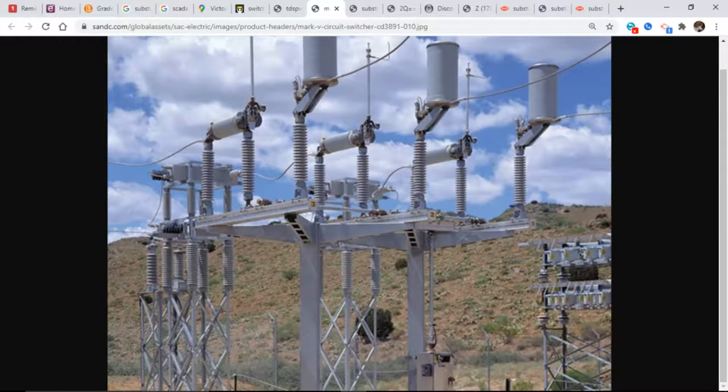Batteries. Hey, you bring up the question, and it was supposed to come up a little bit later once we got through this. We'll go ahead and go through it now. All of your substation automated equipment, including the communications and SCADA, does not run off of 120, 240. A 120, 240 transformer is installed in a substation to charge a battery bank, and that battery bank stays at 48 volts DC. That 48 volts DC then runs all of your equipment. The expected plan is for 24 hours until the batteries are depleted.